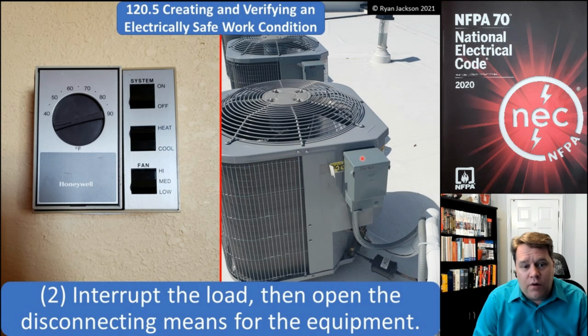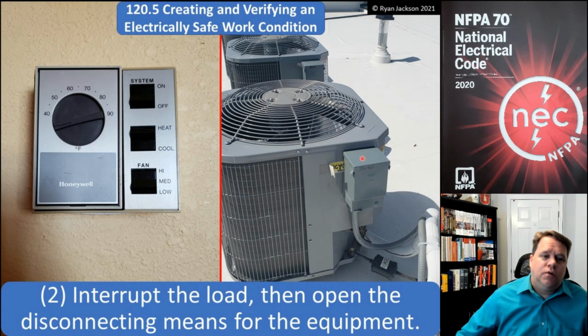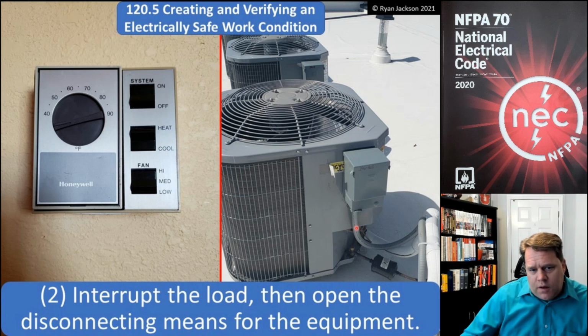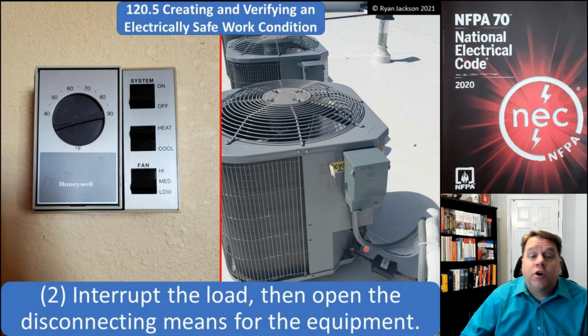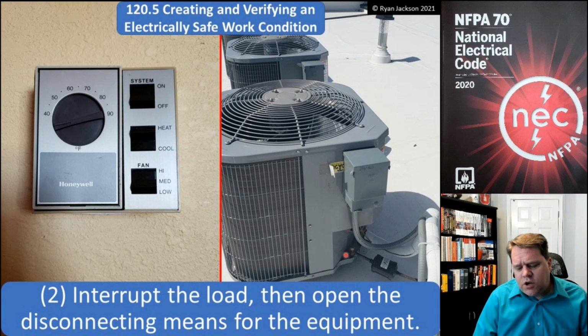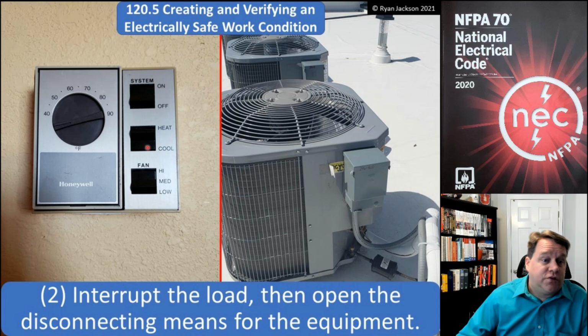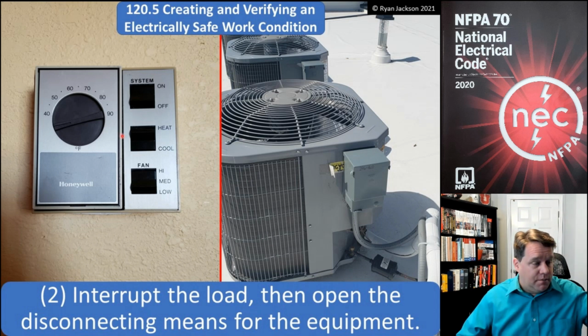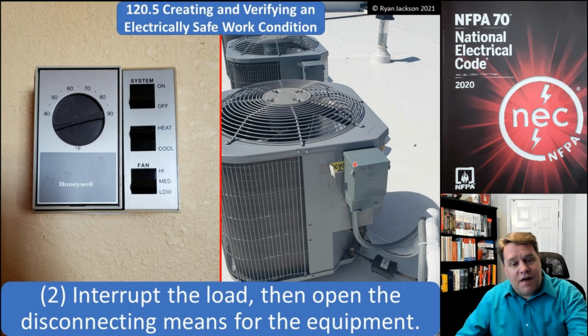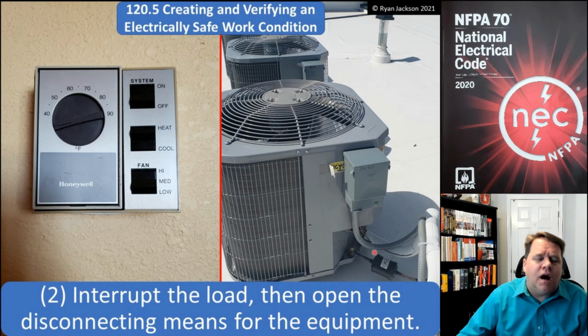Once you've figured out everything that could possibly power up the equipment, now we can start the procedure of shutting it down. So number 2, we're going to interrupt the load, then open the disconnecting means for the equipment. All right, so looking at the photograph here, could I go up to the rooftop and just shut off this disconnect while the air conditioner is running? Sure. Yeah, I could. I could definitely do that. But let me ask you a question. Which do you think is a safer way to do it? Should I just shut off the thermostat first and then get the motor to stop spinning and then go hit the disconnect? Yeah, I think so.